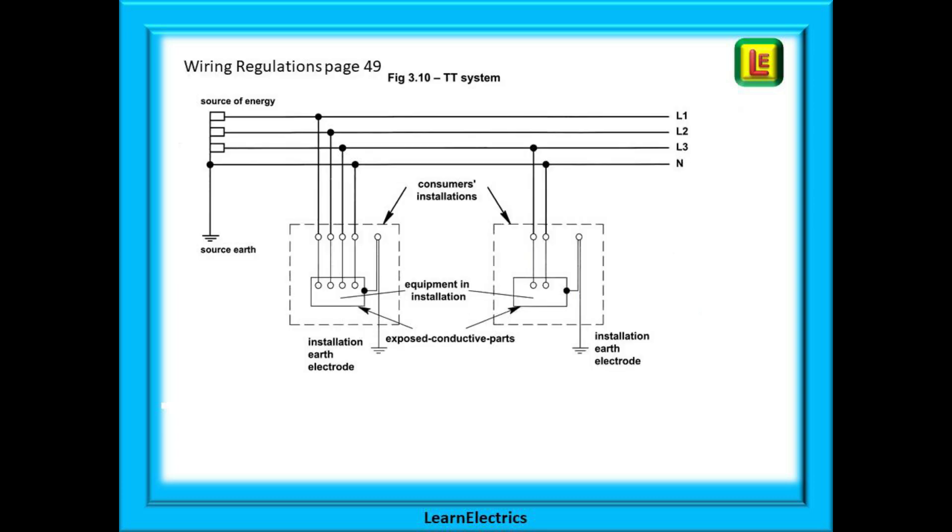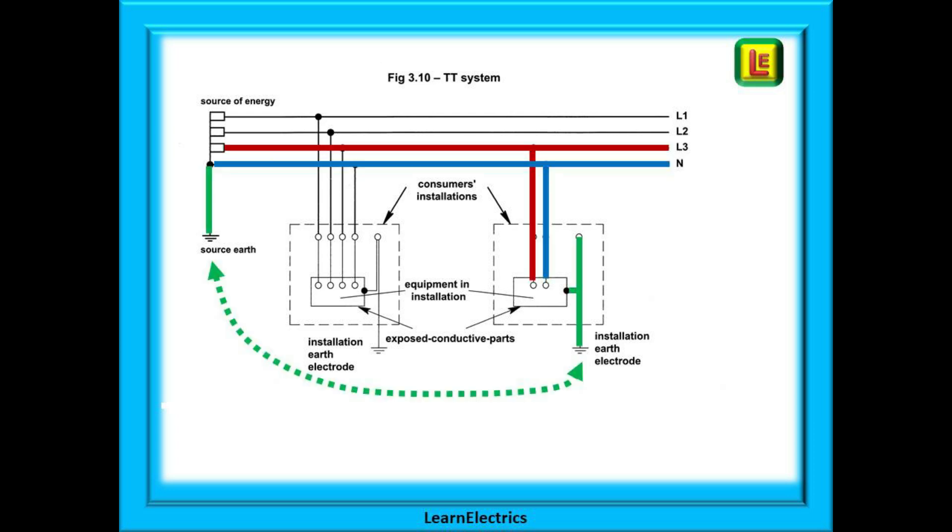On page 49 we see the TT system. Phase and neutral go to the intake position. But the earth does not. At the supply transformer there is an earth rod. At the intake position there is also an earth rod. There is no copper conductor between them. They rely on a connection through the soil.